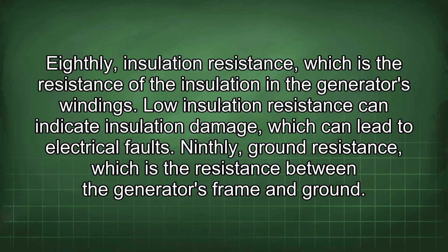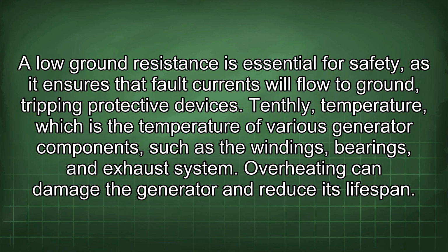Ninthly, ground resistance, which is the resistance between the generator's frame and ground. A low ground resistance is essential for safety, as it ensures that fault currents will flow to ground, tripping protective devices.